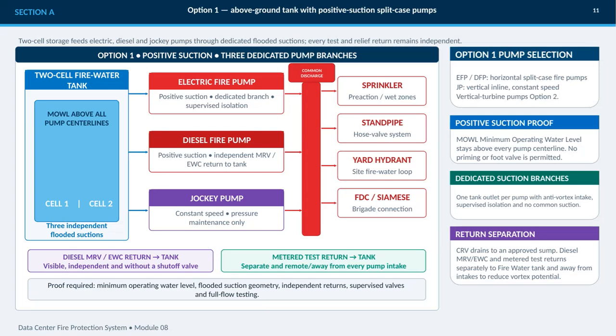This slide presents option 1, an above-ground, 2-cell firewater tank serving 3 dedicated pump branches. The key design principle is positive suction. The minimum operating water level remains above every pump centerline, so the pumps have flooded suctions and require neither priming nor foot valves. The electric and diesel fire pumps use horizontal split case configurations, while the jockey pump is vertical inline and maintains system pressure. Each pump has its own tank outlet, anti-vortex intake, and supervised isolation. There is no common suction, which helps preserve independence and reliability.